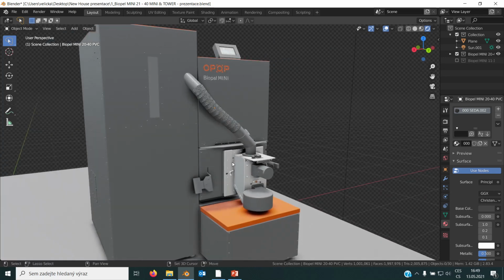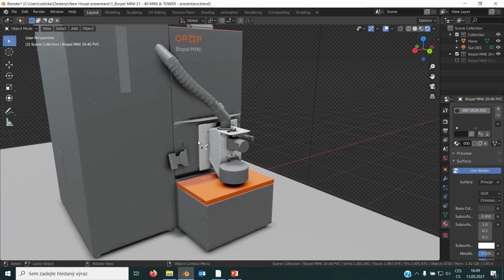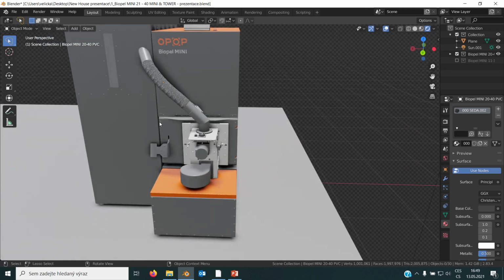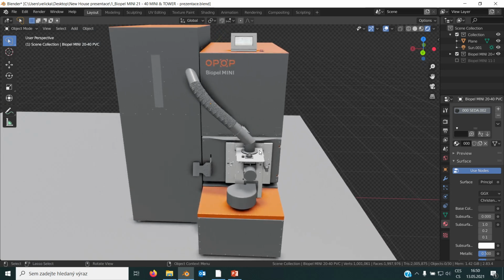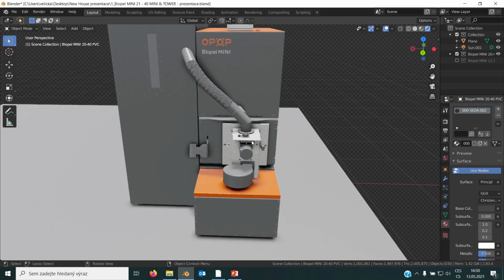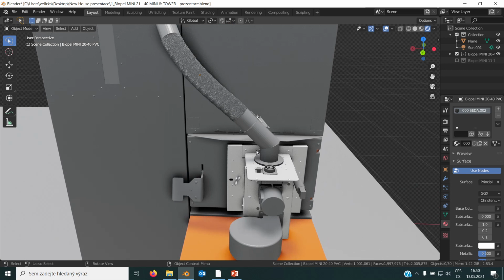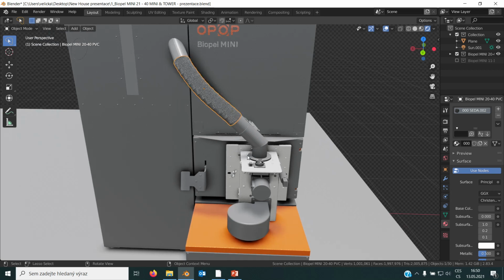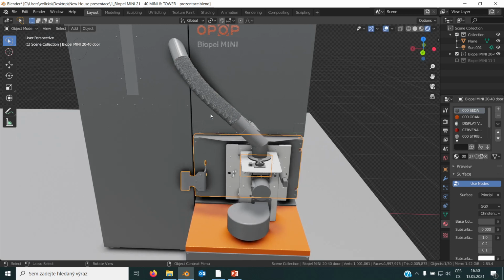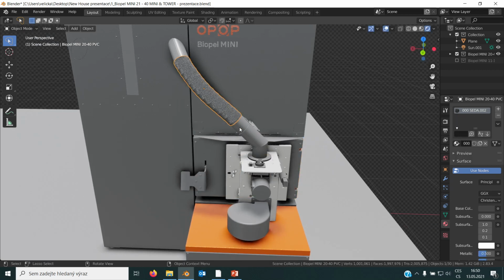Next thing is that when you start the boiler, of course there is a combustion process inside, and the doors are designed so that you cannot open the door fully during operation, because there is a flame inside, and you want to make sure that no flame goes out of the boiler. Okay, so we achieve this safety by two things. First of all, when the PVC hose is connected and you want to open the door, it allows you to open the door just a little bit, because the connection between the feeder and the burner with the PVC hose is tight, and you basically cannot open the door fully.